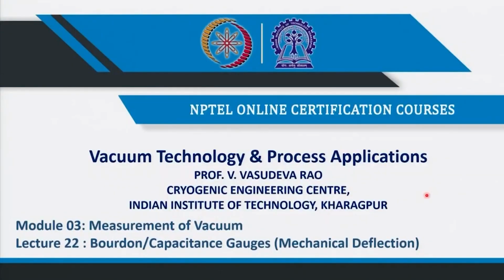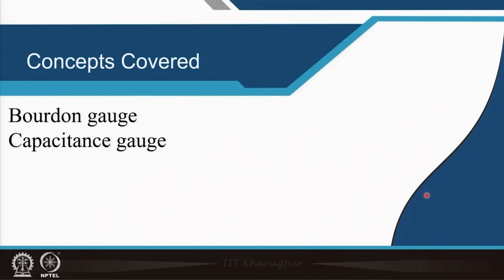With this introduction, I will not bore you much further. Let us go to these two gauges, since we have to complete the syllabus - we will see the Bourdon gauge and the capacitance gauge today. Why have I clubbed these two gauges together? Both depend on mechanical deflection due to the forces created by pressure differences. In a way these are primary forces from pressure differences, but they are not as accurate as a U-tube manometer or McLeod gauge, since those are defined directly with respect to millimeter of mercury, which is itself the unit. So these are slightly different standards, but still quite good, rugged gauges. In this lecture we will discuss the Bourdon gauge, the capacitance gauge, their working principles, and some idea about their limitations.